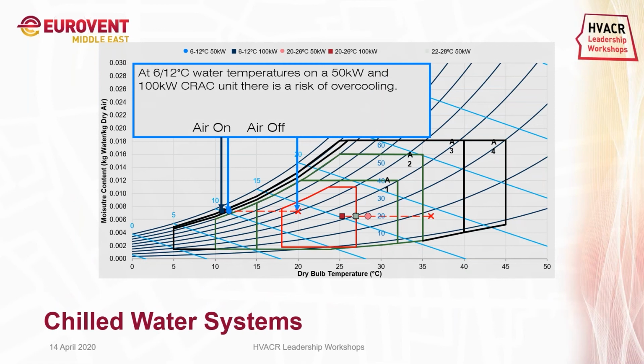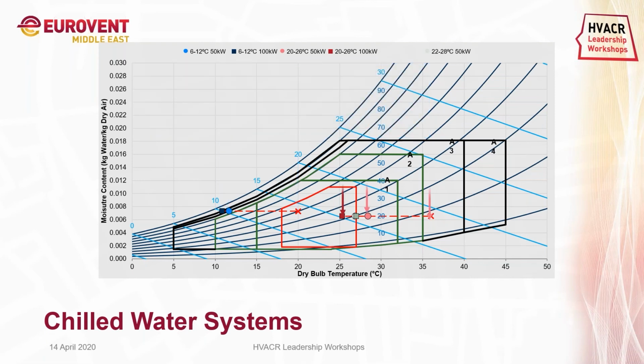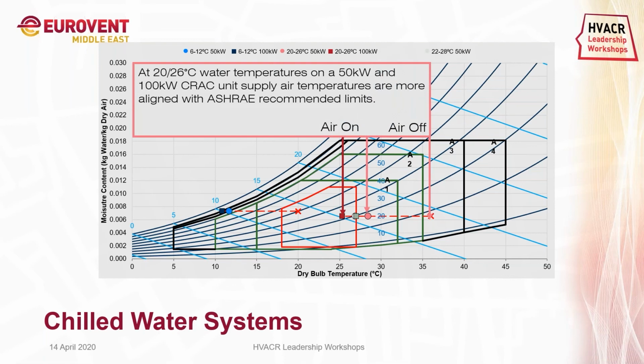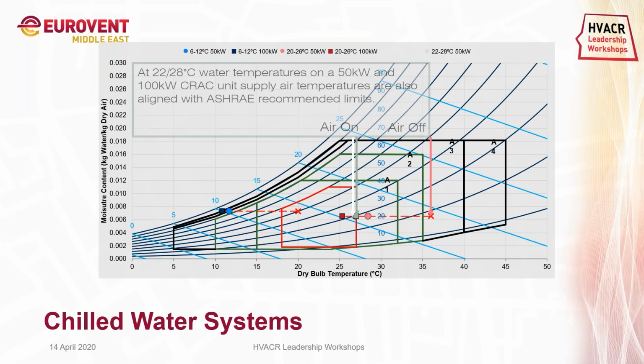Now, these temperatures are plotted against the ASHRAE guidelines. At 6/12, you can see we have taken 2 facilities, 50 kilowatt and 100 kilowatt. The air on temperatures are well below the recommended range, and we are seeing a risk of overcooling there. At 20/26, for a 50 and 100 kilowatt, supply air temperatures are more aligned with the ASHRAE recommended limits, as you can see in the plots. At 22/28, the supply air temperatures are also aligned.